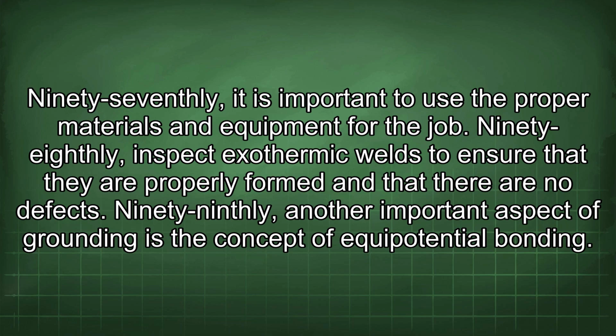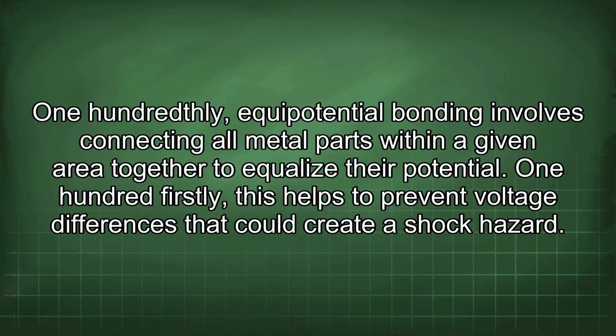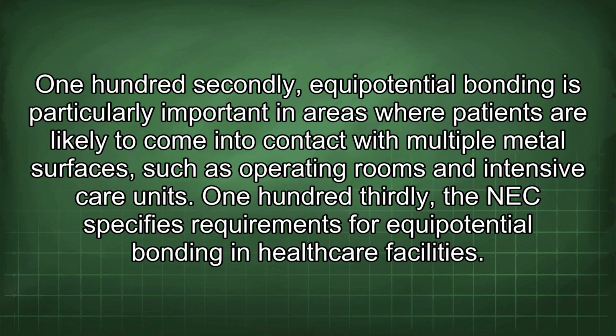99th, another important aspect of grounding is the concept of equipotential bonding. 100th, equipotential bonding involves connecting all metal parts within a given area together to equalize their potential. 101st, this helps to prevent voltage differences that could create a shock hazard. 102nd, equipotential bonding is particularly important in areas where patients are likely to come into contact with multiple metal surfaces, such as operating rooms and intensive care units.